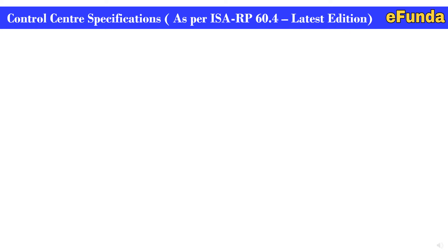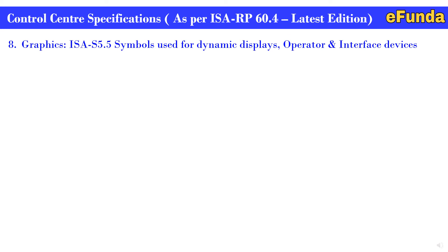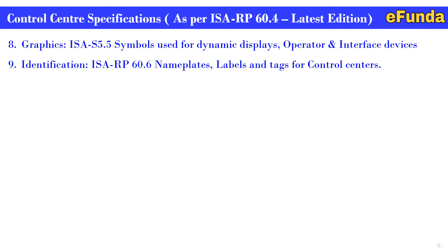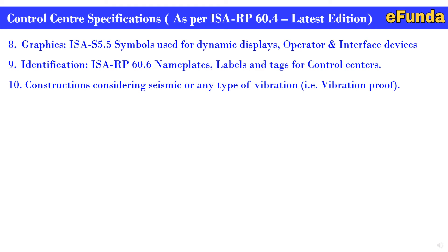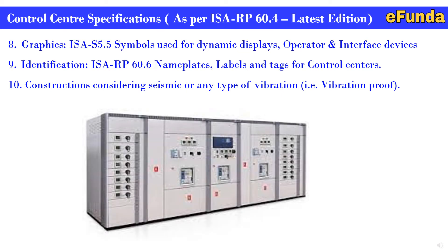Eighth point: graphics — ISA S5.5 symbols used for dynamic displays, operator and interface devices. Ninth point: identification — ISA RP 60.6 name plates, labels, and tags for control centers. Tenth point: construction considering seismic or any type of vibration — that is vibration-proof design. These are all the specifications considered while designing the control center. One can see the photograph where the latest standards are applied and construction of the control center panel is done systematically and aesthetically. This is how the control center should be covered with minimum requirements as per ISA RP 60.4 and client specification.